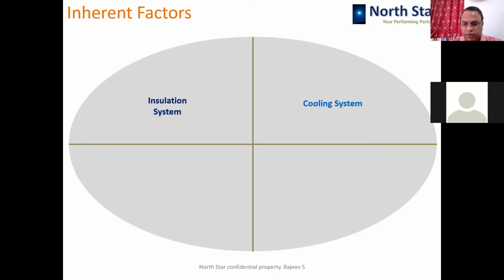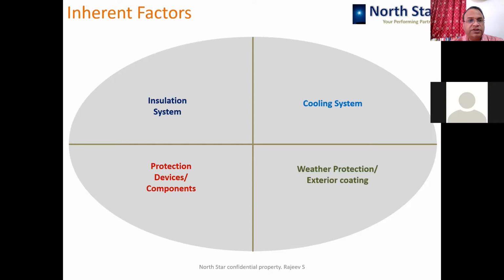Then cooling system, again it is related to the insulation life because the temperature decides the aging rate. We have understood in our previous programs that the loading and increase in the temperature directly affects the insulation life and quality. Protection devices and components, whether they are functioning, rightly selected, and rightly set as per the requirement. So that plays a very important role. And weather protection and exterior coating, that is primarily the enclosure and the painting.